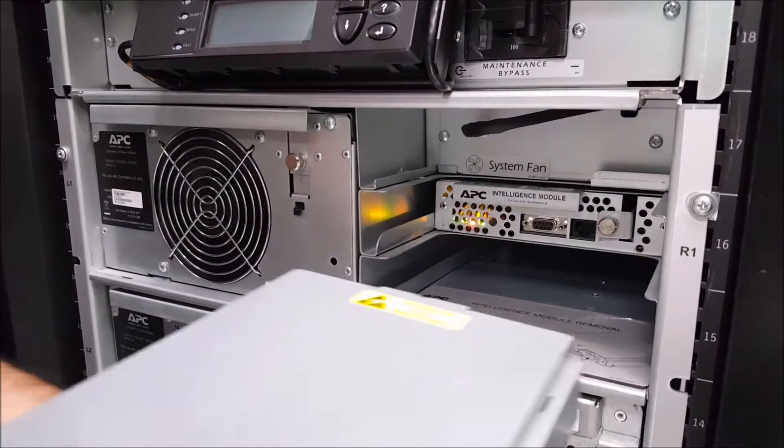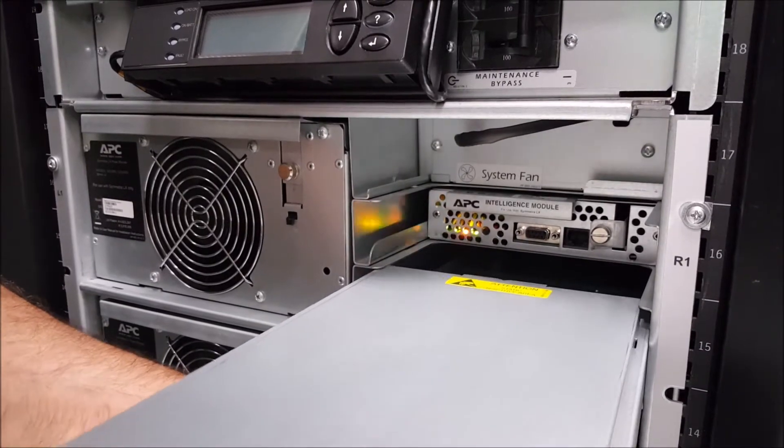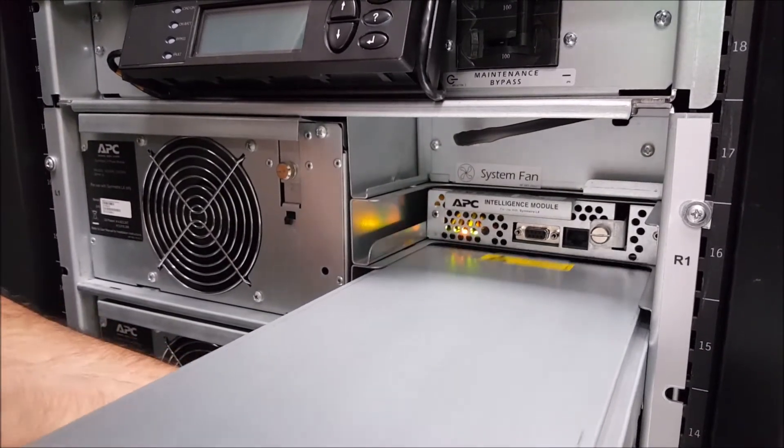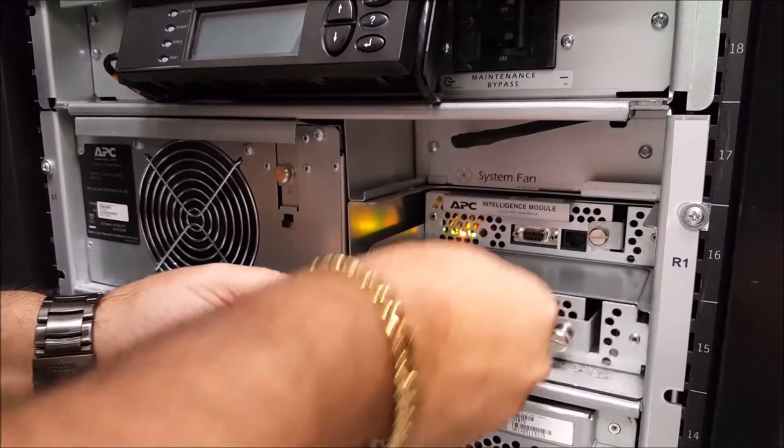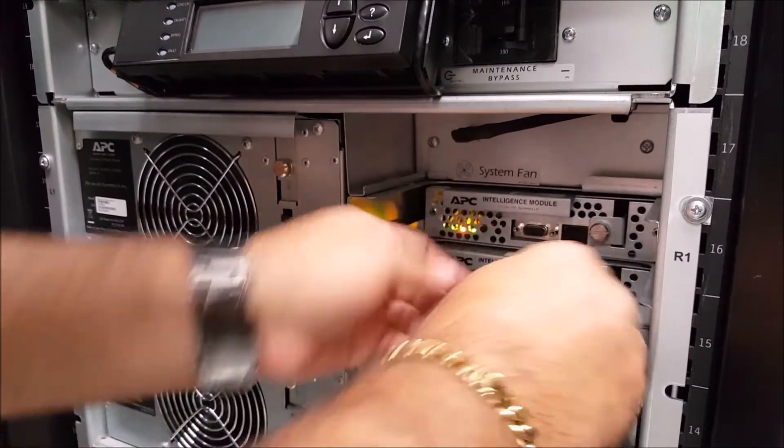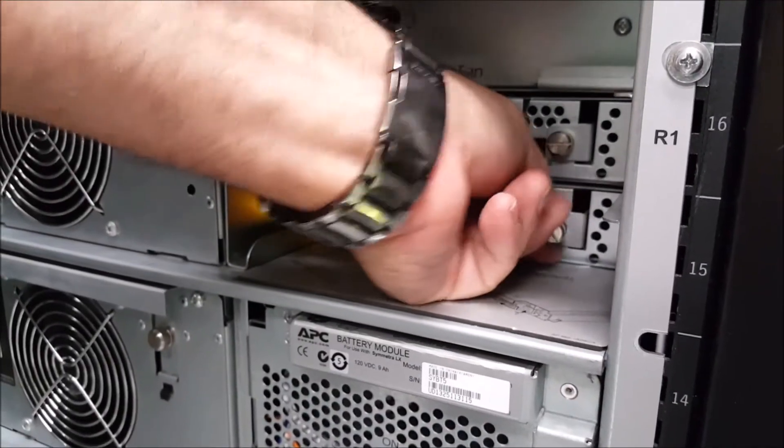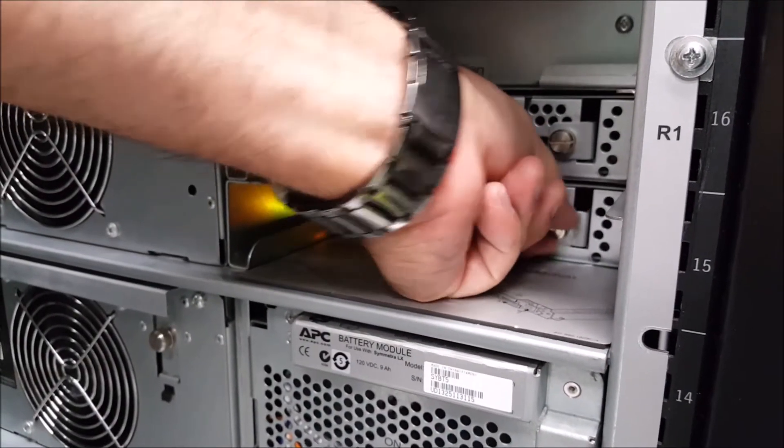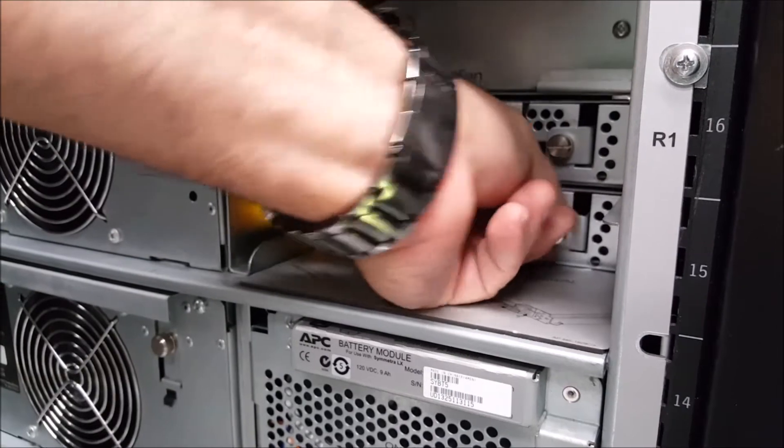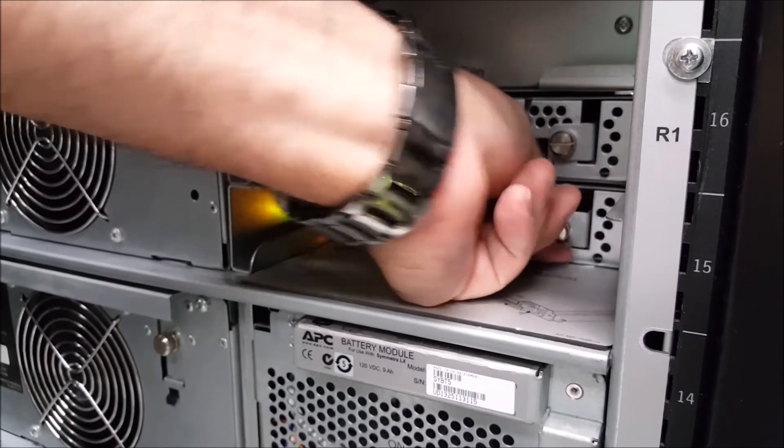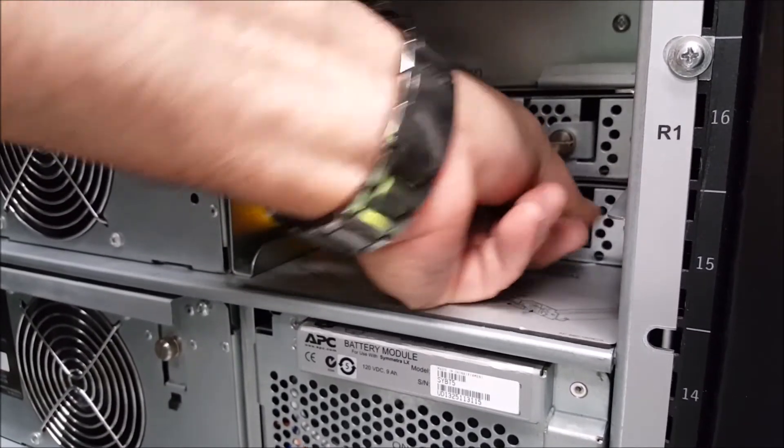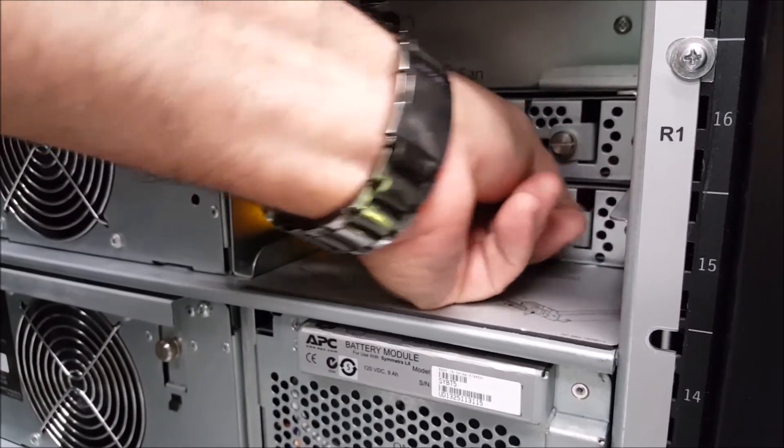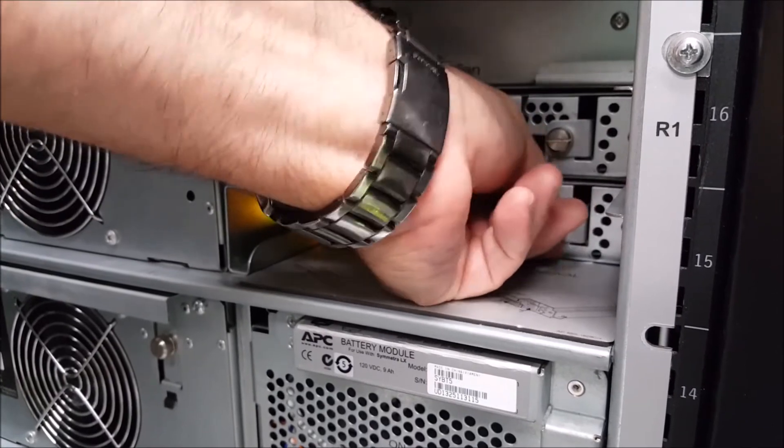Next, slide the intelligence module back into the Symmetra UPS. Once the intelligence module is inserted all the way back and making a good connection, you'll want to move the metal bracket that the thumbscrew sits in over to the right position to lock it into the chassis and then tighten the thumbscrew down to secure it.